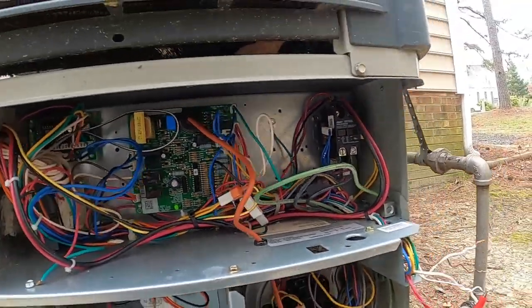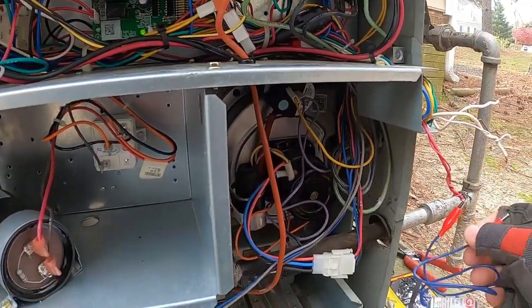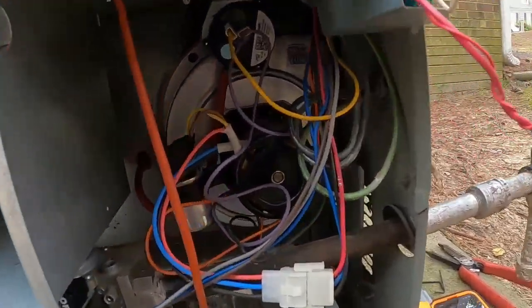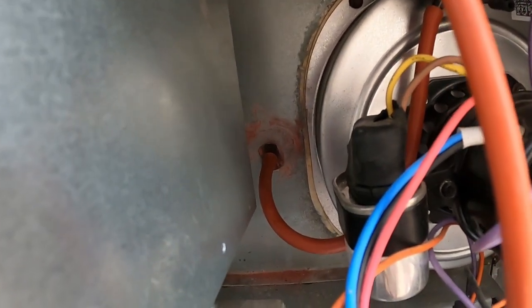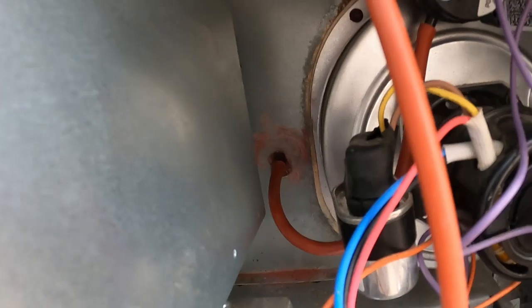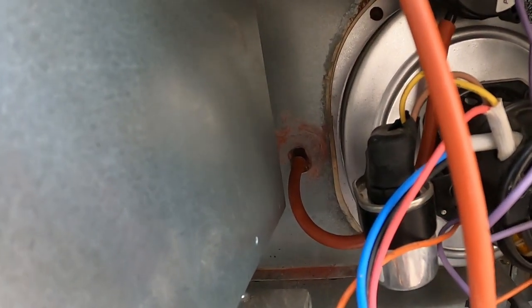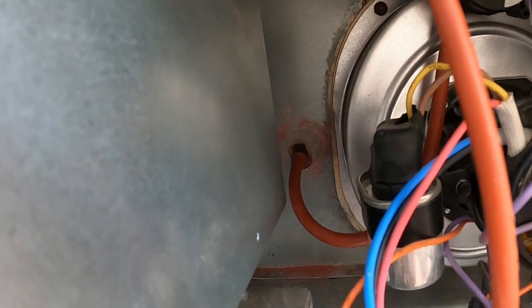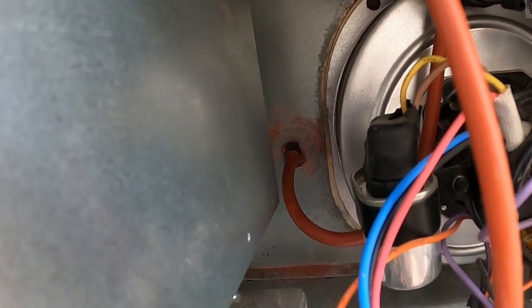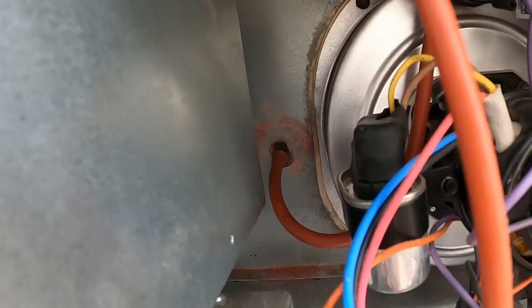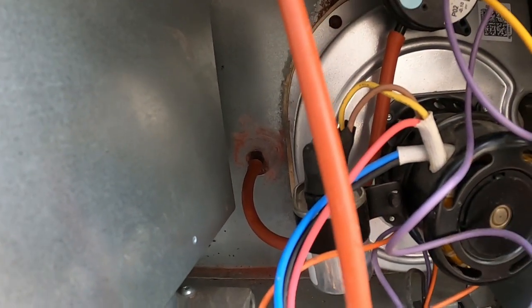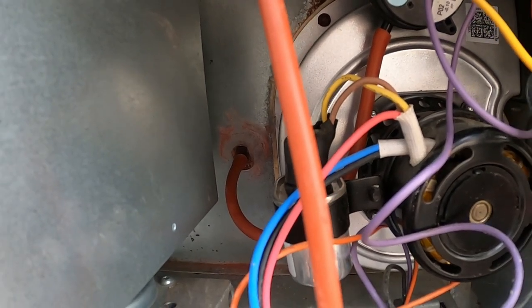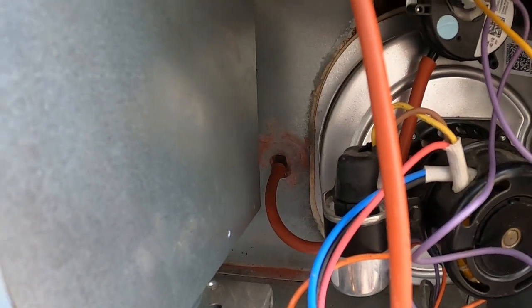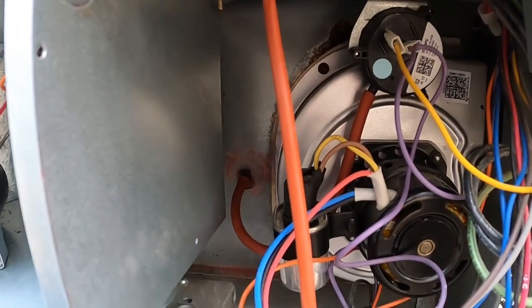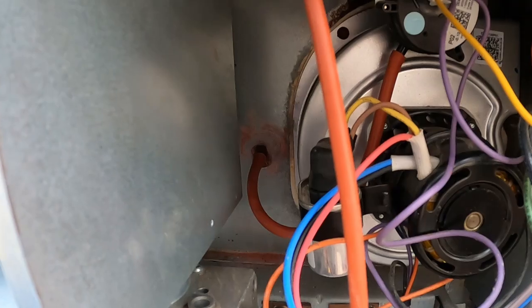And if it was just that, this unit's 11 years old, I'd say probably fix it, but if I'm not mistaken, this whole heat exchanger has to be replaced because it comes all together as one assembly to fix that problem. I mean, I could bore that out and put an access fitting or something, screw something in there and seal it up. But that's just not the proper way to fix a gas furnace. So it is what it is. We're gonna give him his options and see what he wants to do.